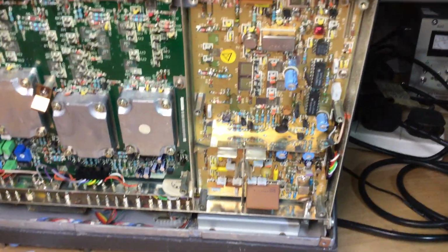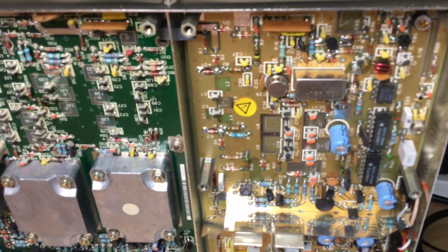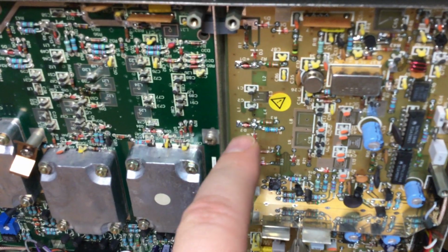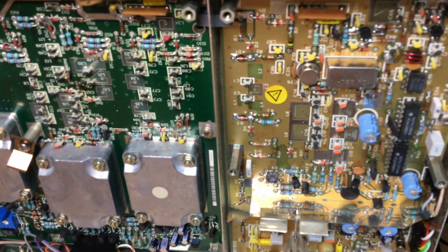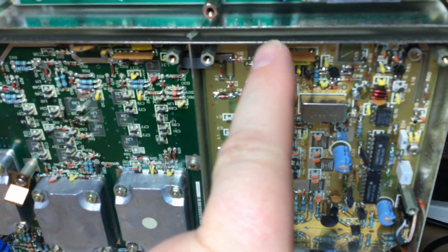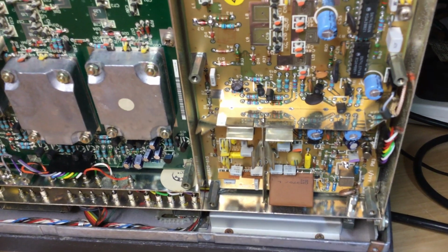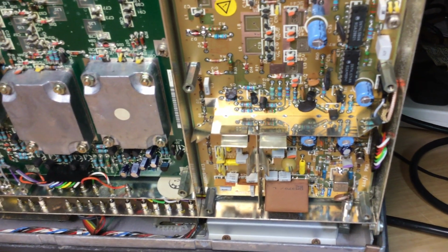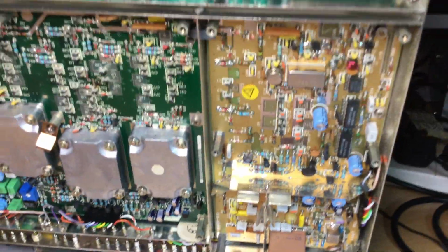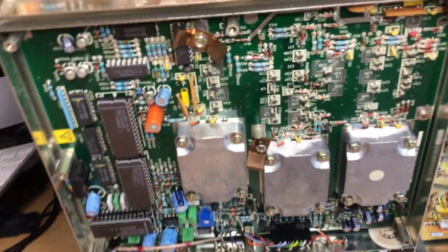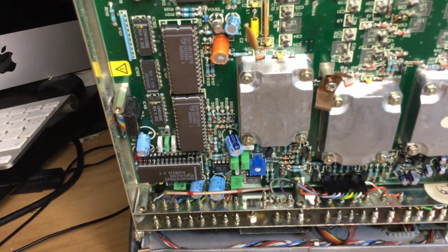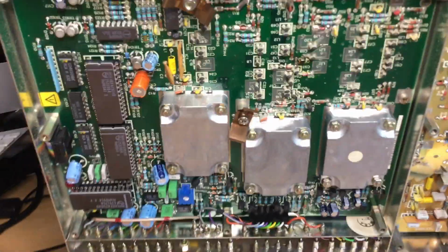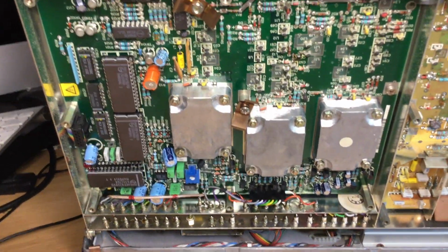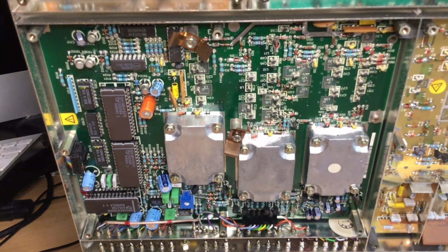can change them. Now, we were talking earlier about pin diode attenuators. That's what these are. These are the pin diode attenuators, and they then control the RF level going into the amplifier before it's then passed through to the output, and obviously fed off then via the step attenuator to the front panel. So that's that section. This board here is the RF Synthesizer Board. So this is basically the phase lock loop, the PLL board, which locks the frequency of the instrument.